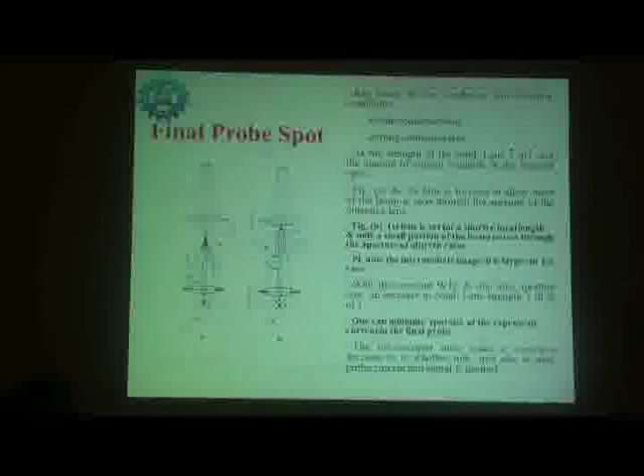Here also you have the short working distance and long working distance. The working distance is nothing but the sample position from the tip of the final pole piece. So you can increase and decrease the working distance from the pole piece, downward or upward. If you go upward, you are working at a short working distance.